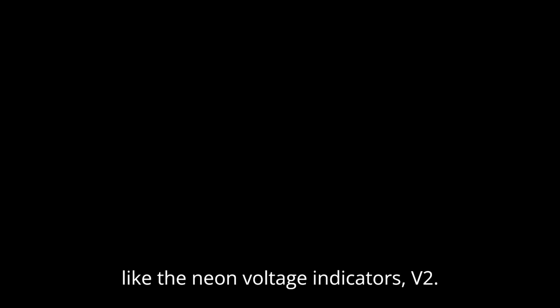Safety and indication are equally crucial when faults happen out of sight underground. What about locating the problem quickly? How do you know which fuse blew? That's handled by features like the neon voltage indicators, V2. These indicators attach directly to the capacitance test points of the elbow. Okay, and what do they show? If the CLF inside the EFXE operates and clears the fault, the load side is de-energized and the neon lights just stop flashing. That immediately signals a blown fuse indication to the personnel without them having to physically open the vault or perform complex testing.